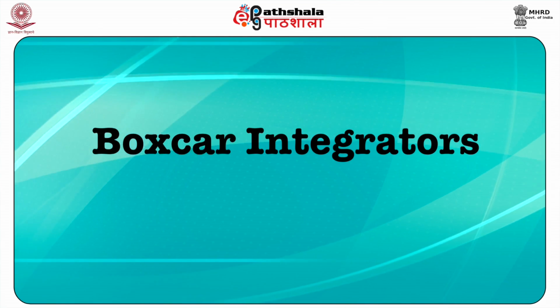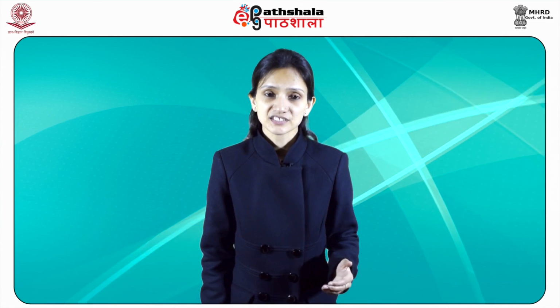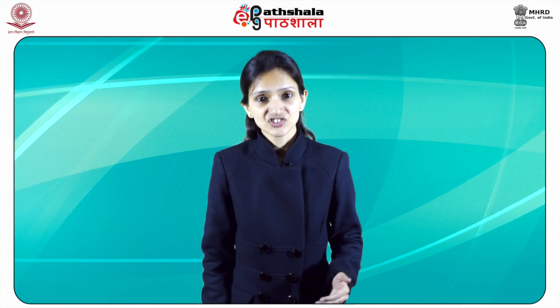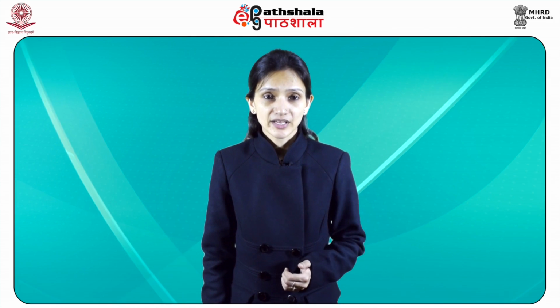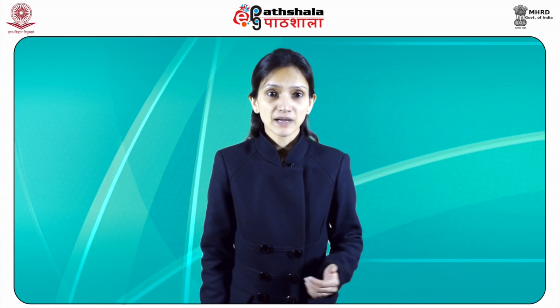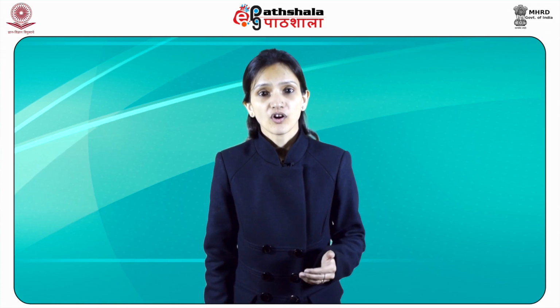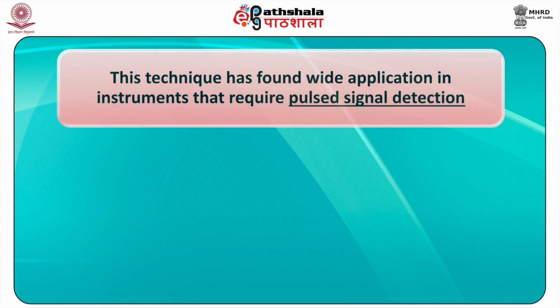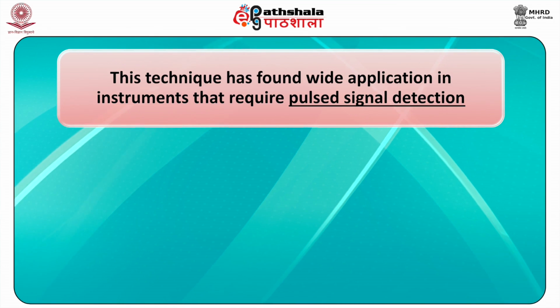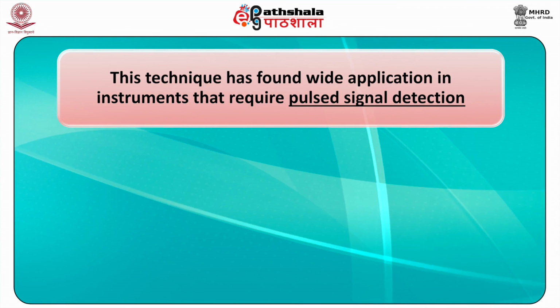Next is boxcar integrators. The boxcar integrator is a relatively simple method of signal enhancement for repetitive signals. It periodically samples the same portion of a signal for a fixed period of time and then averages the samples using a low-pass RC filter. This triggerable gated integrator is a versatile measurement device. It provides S/N enhancement for the portion of the signal that is sampled. This technique has found wide application in instruments that require pulsed signal detection.